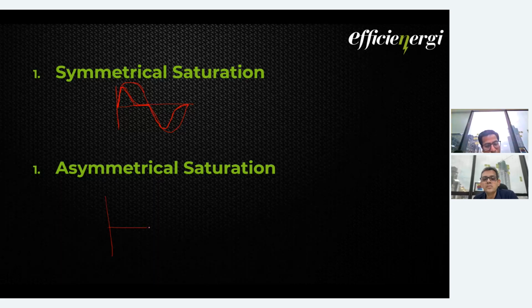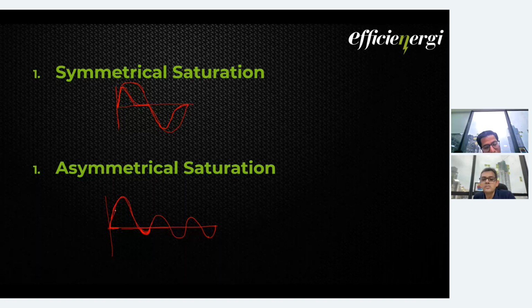In asymmetrical saturation, what happens? Asymmetrical means the waveform is not symmetrical across the origin line. So this is your origin, and it is not symmetrical across. In a positive cycle the magnetic dipoles start to orient, but the level is not up to the saturation level. In the negative half, you can see it is very small, so a very small number of dipoles get aligned to the reverse direction. Then again it starts to align in the positive, but most of the dipoles have already aligned in the positive, and very few go to the reverse direction. When this cycle comes again, there are very few dipoles left in the reverse direction, and because of this you will get a very heavy saturation. So this will be the secondary current.